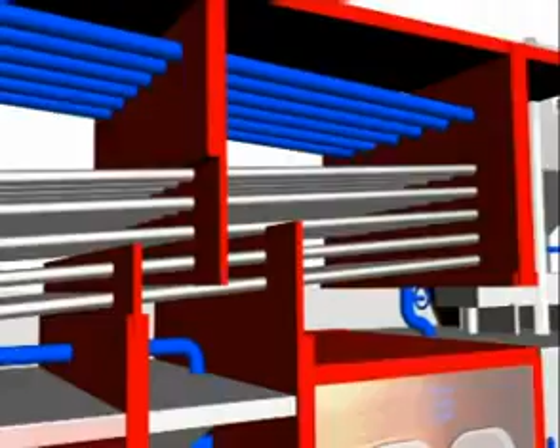Heat transfer. The furnace in-bed cooling tubes transfer radiant heat of the FBC furnace bed, and at the same time these tubes control the furnace temperature to avoid clinker formation. That is why these tubes are called cooling tubes.